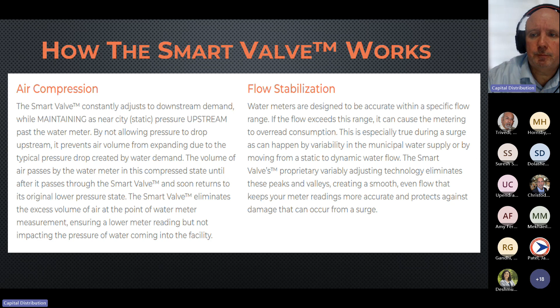On top of that, because there will be a drop in pressure after the smart valve, it's going to maintain the pressure at the meter. Then afterwards, there'll be a drop off, and that's based on where you set the valve to. You're going to get reduced consumption up the line. Again, if you're showering for 5 minutes and it's at 70 psi when it reaches you, you're going to use X amount of gallons of water. If you reduce that down to 60 or 55 or whatever the number is, you're going to use less. So there'll be a reduced consumption.